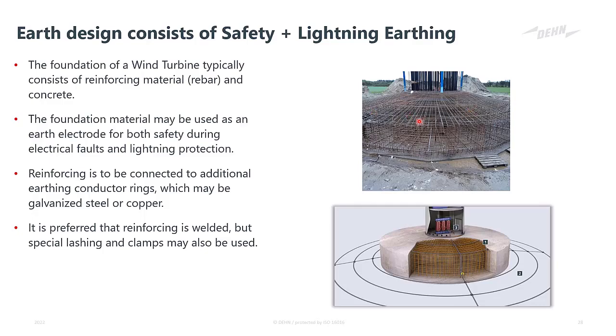Now, the foundation material is used as the majority of the safety earthing, but in the case of lightning protection, we require that the reinforcing is welded at all these joints, welded very properly, or lashed quite extensively. And this is typically not done in industry. So what we do is we add lightning conductor within the foundation. You can see there the silver conductor there, and we clamp it to the rebar every 2 to 5 meters, creating these rings, and they basically just form bonding to make sure that the connection between all the rebar is very good and is able to withstand mechanical force during a lightning strike. Otherwise, if you don't do that, the lashing and things like that can go loose during a lightning strike, and it can cause mechanical damage and break off parts of the concrete and so on.